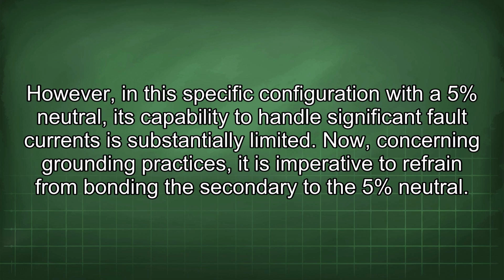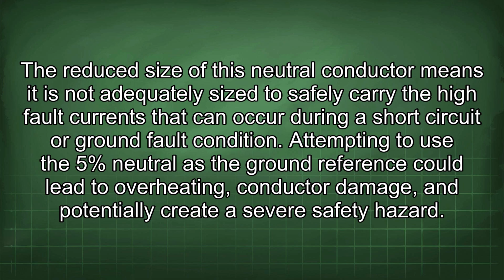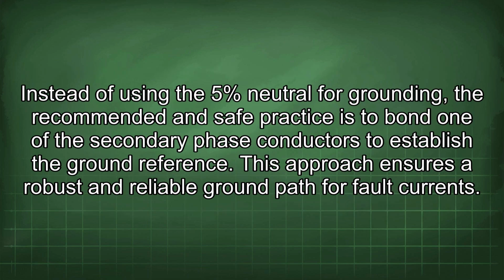Now, concerning grounding practices, it is imperative to refrain from bonding the secondary to the 5% neutral. The reduced size of this neutral conductor means it is not adequately sized to safely carry the high fault currents that can occur during a short circuit or ground fault condition. Attempting to use the 5% neutral as the ground reference could lead to overheating, conductor damage, and potentially create a severe safety hazard. Instead of using the 5% neutral for grounding, the recommended and safe practice is to bond one of the secondary phase conductors to establish the ground reference. This approach ensures a robust and reliable ground path for fault current.